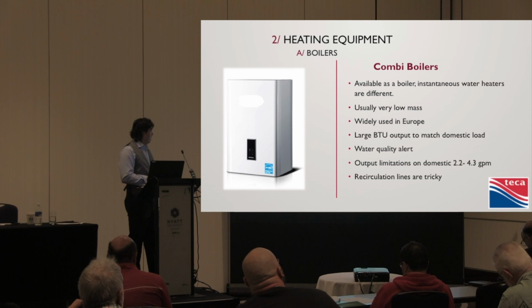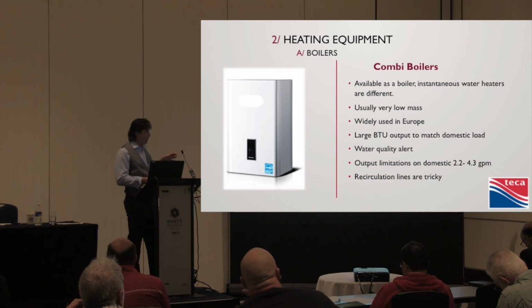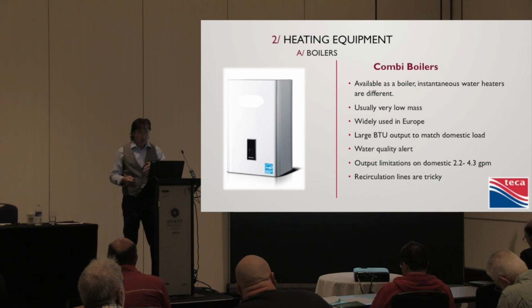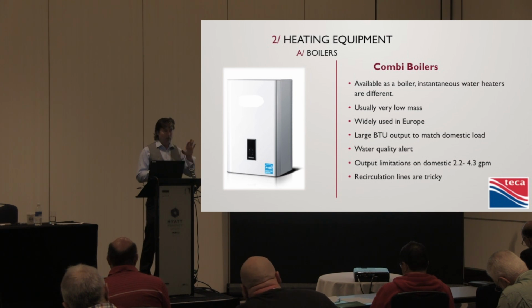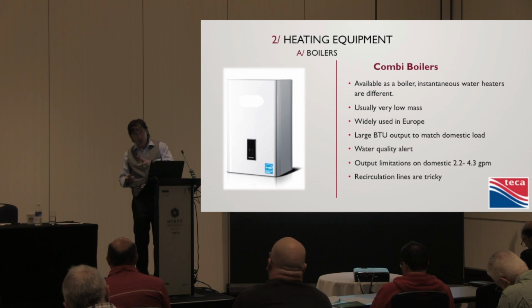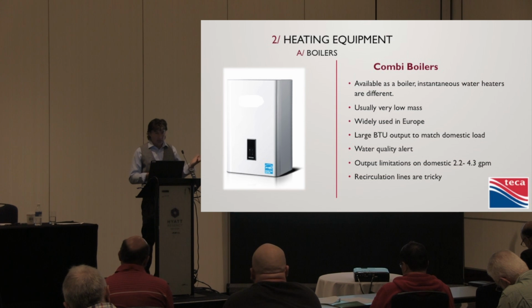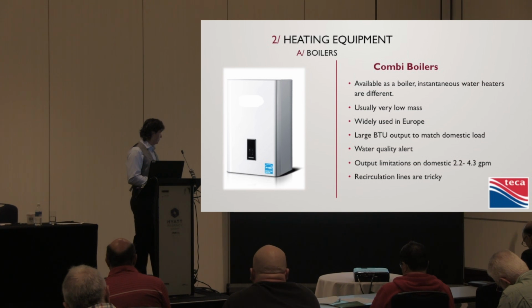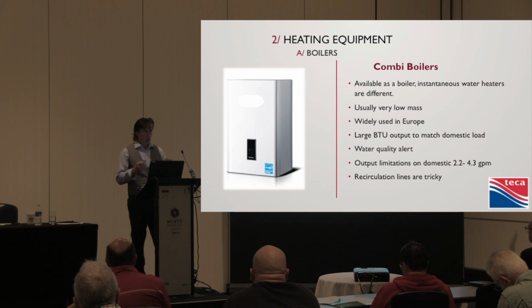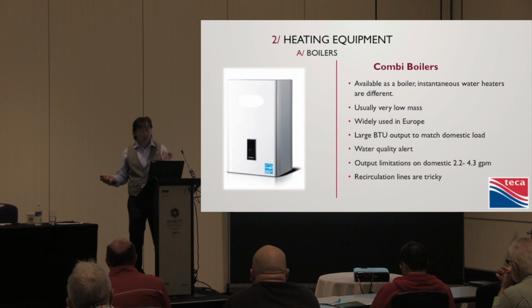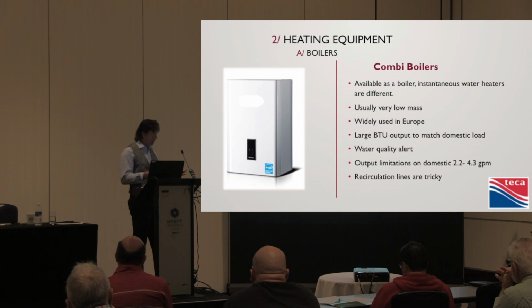Combi boilers. When we call it a combi boiler, we've got to be careful. There's instantaneous water heaters, and then there's combi boilers. The boiler guys don't like the instantaneous guys calling their stuff boilers because there's different CSA regulations around boiler manufacturers as opposed to water heater manufacturers. So we're talking about combi boilers here. Also very low mass. What they have inside is normally a heat exchanger. So you've got a boiler that's doing space heating as well as domestic heating, usually with a built-in heat exchanger. You're there anyway, you already got the one burner. Let's just turn on a pump and circulate to a heat exchanger, produce domestic water instantaneously, or let's produce heating water on the other side.